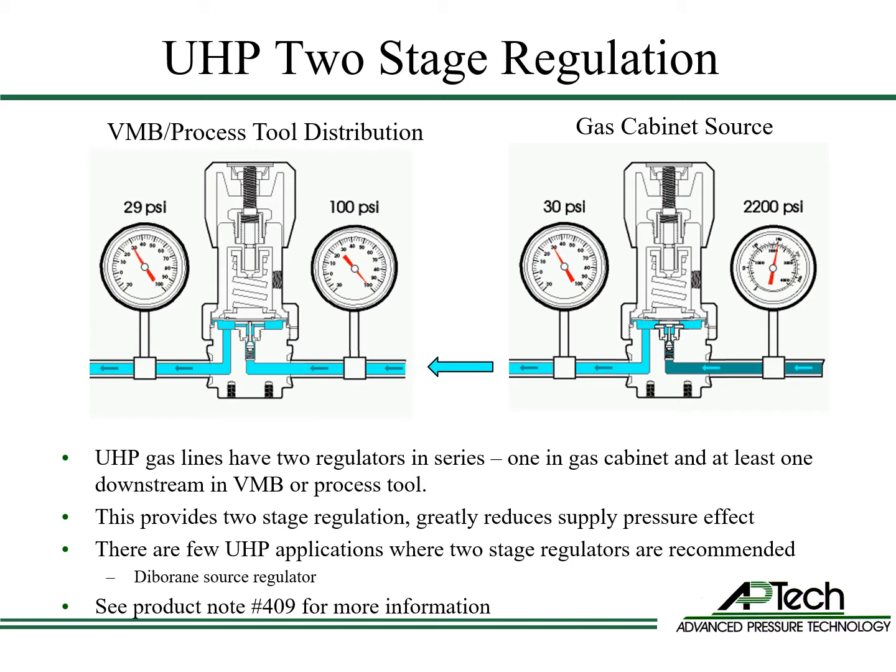Ultra-high purity applications utilize two-stage regulation using two regulators in series — one in the gas cabinet and at least one in the valve manifold box or in the process tool. This provides two-stage regulation and greatly reduces supply pressure effect. Few ultra-high purity applications use a dual-stage regulator as the source; diborane gas is one example. Go to AP Tech's website for more information, including product note number 409, which describes two-stage regulation for semiconductor manufacturing applications.